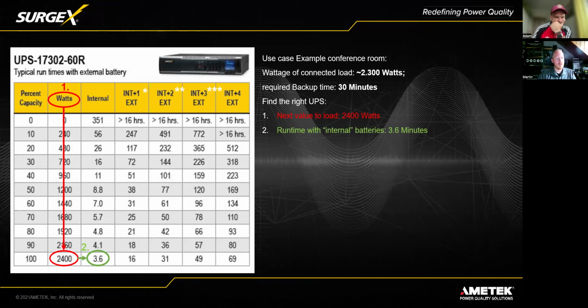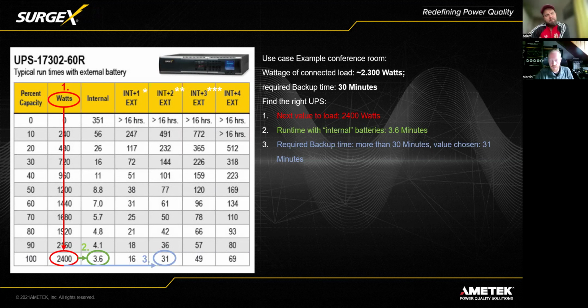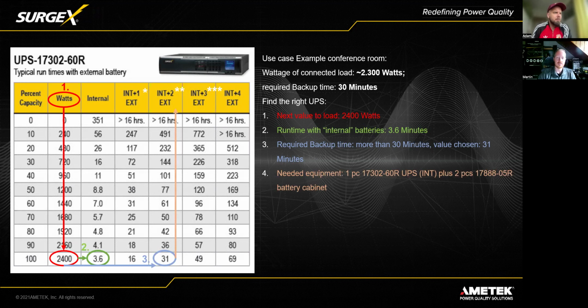That's not enough, since we need half an hour. So we'd move along the same line, staying on that wattage, until we find a value more than our 30 minutes — in this case, 31 minutes. Then we jump back to the top, where it says 'int plus ext 2x', meaning the 31 minutes is the runtime on internal batteries plus two external battery cabinets.